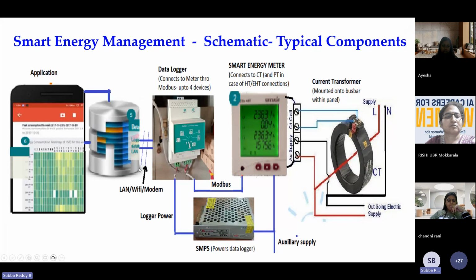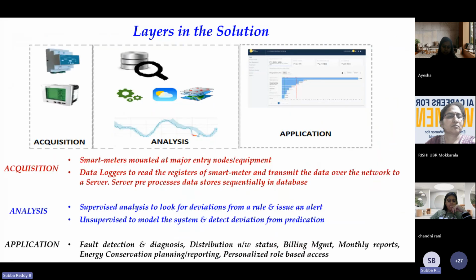Then we had various application softwares which we tried to develop, and this application software generally has 3 layers, as I mentioned - the data acquisition happened, then the analysis. What type of analysis? So for data acquisition, we used smart meters which were mounted at major entry points in the campus. We had data loggers to read the registers of the smart meter and transmit the data, and the server was used for pre-processing, storing of the data sequentially in a database.